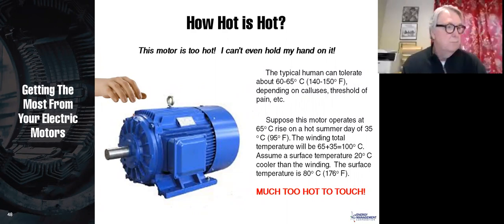Great. Very related to that question, and possibly already covered, is what is the best insulation type for VFD-driven motors? Yeah, so you want Class F insulation, and I say you want it because it's free. Generally, for motor manufacturers, it's a standard insulation. You're not going to pay any more for Class F insulation than you are for Class B. Class H, people still charge a premium, so I'm not recommending you use Class H, even though that's a little better insulation. But we would recommend for a VFD that you get Class F insulation with a Class B rise, that you have a cast iron motor, and that you have at least 1.15 service factor.